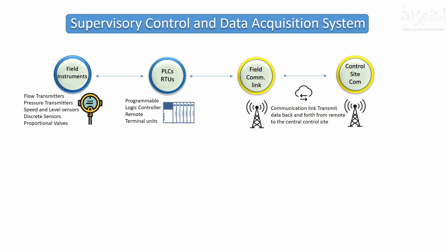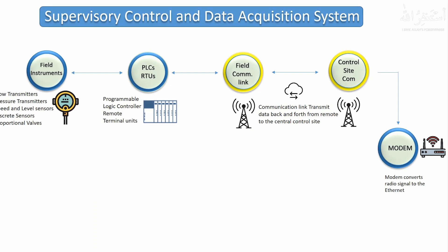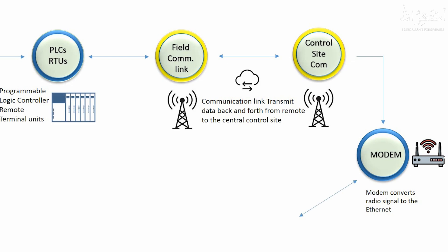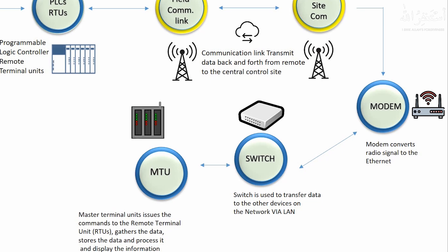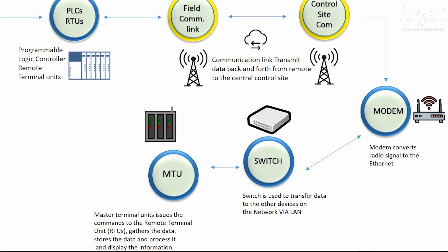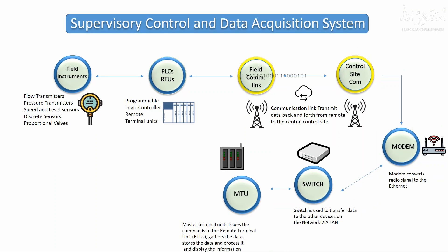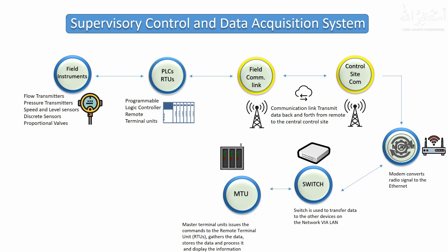Once the data is received at the central control site, it is converted to Ethernet using a modem. After that, the modem is connected to an Ethernet switch, which acts like a central LAN hub. This switch is connected to the MTU — Master Terminal Unit. The Master Terminal Unit receives data from the RTUs or PLCs, stores it, analyzes it, and sends control commands back to the RTUs to control the process at the remote location.